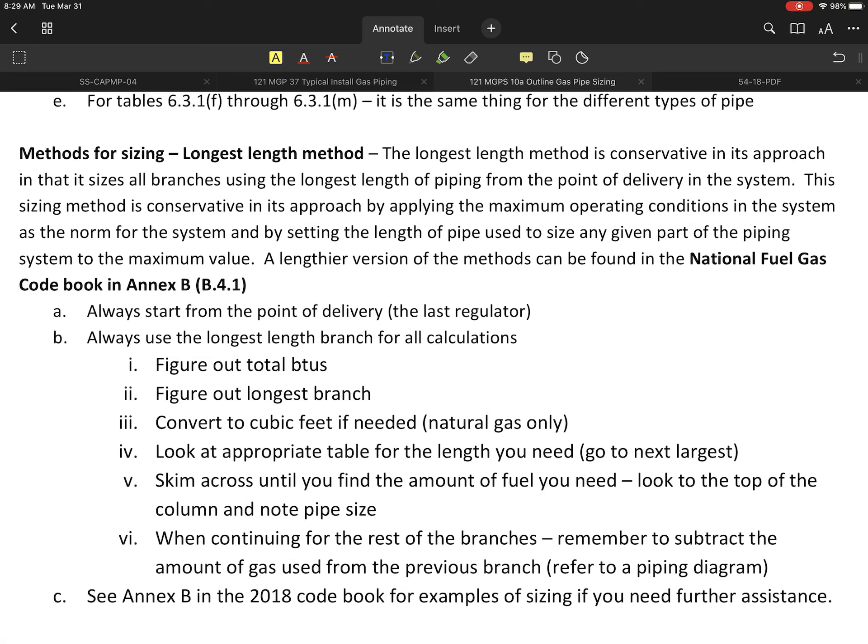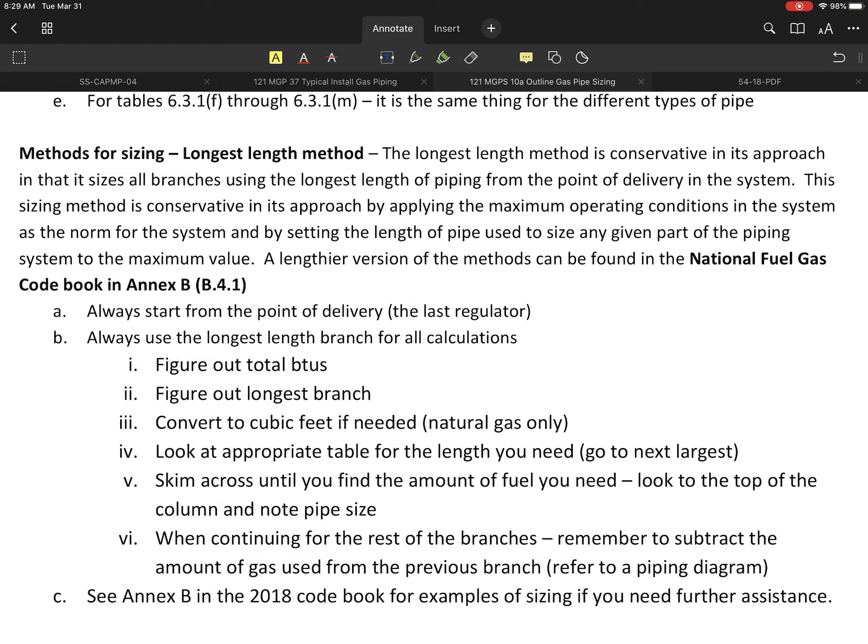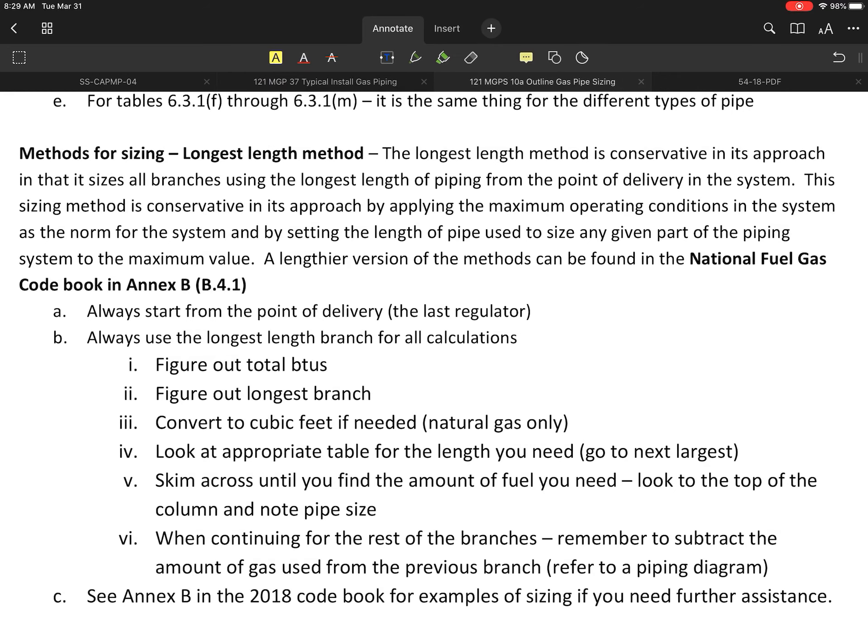A little bit about this particular method: the longest length method was probably the original method used by most application people in our field. This method is what I would consider a very conservative approach where we size all the branches, the main, everything using the longest length of the piping section from the point of delivery. It's essentially assuming that even the short runs will use that longest length for this application.